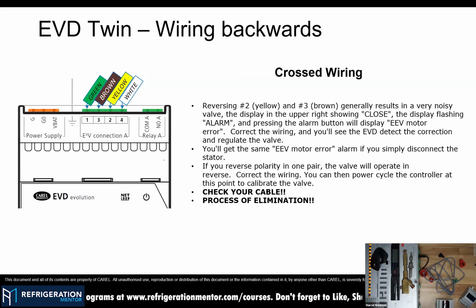If you simply replace brown with green or yellow with white, what we would be doing is sending the current in the wrong direction inside the motor, and this would make it so that instead of opening the valve, we are closing the valve, or the other way around. So this would generate a lot of confusion. It will not trigger an alarm because we are reading the currents, but it will drive the valve in the opposite direction. So make sure that you are properly set with that.